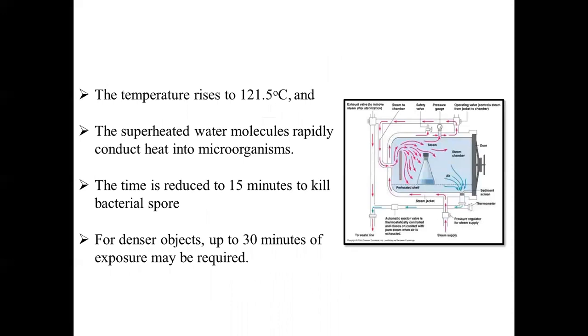Temperature rises to 100 to 121.5 degrees Celsius and the superheated water molecules rapidly conduct heat into microorganisms. So the time we keep it will help in killing the microorganisms in the particular material or equipment. For denser objects, we want to give up to 30 minutes of exposure. Denser objects means particularly glass containing the sample or culture, so we have to keep it for more time.